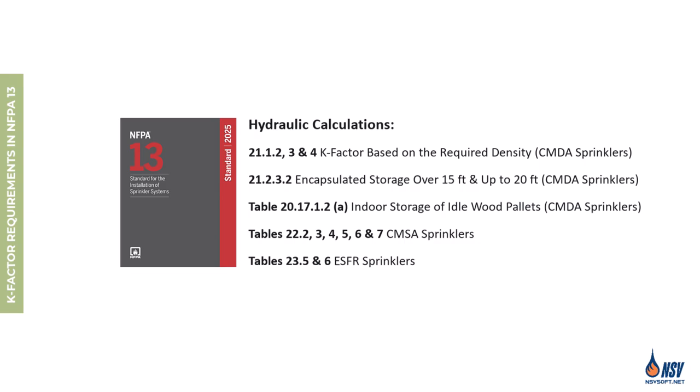NFPA 13 provides detailed tables listing both the K factor and the minimum required pressure, which together help determine the minimum flow rate needed for each sprinkler. Although the requirements mentioned do not cover every detail, they serve to highlight the importance of the K factor in designing fire sprinkler systems.